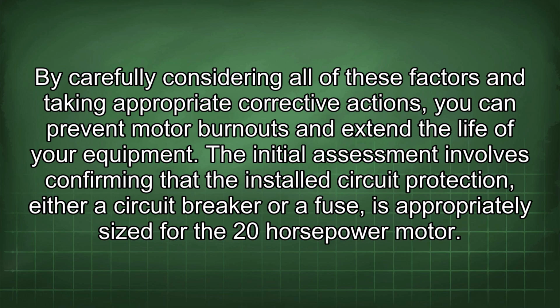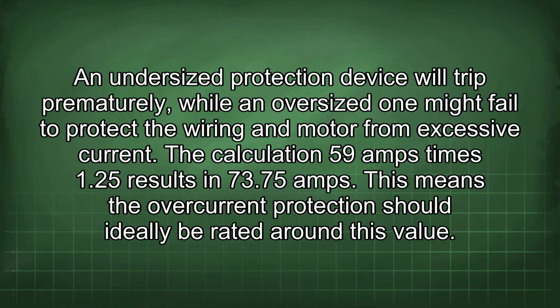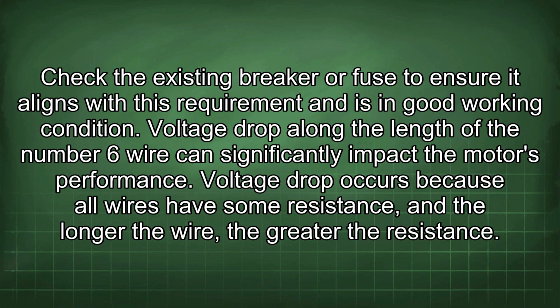The initial assessment involves confirming that the installed circuit protection, either a circuit breaker or a fuse, is appropriately sized for the 20 horsepower motor. An undersized protection device will trip prematurely, while an oversized one might fail to protect the wiring and motor from excessive current. The calculation 59 amps times 1.25 results in 73.75 amps. This means the overcurrent protection should ideally be rated around this value. Check the existing breaker or fuse to ensure it aligns with this requirement and is in good working condition.